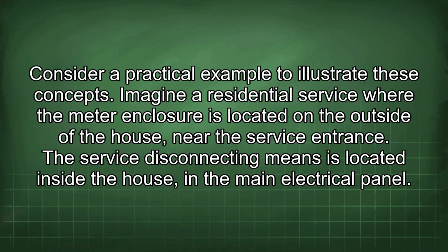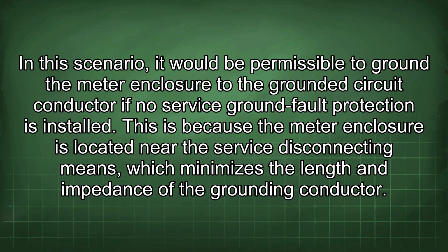Consider a practical example to illustrate these concepts. Imagine a residential service where the meter enclosure is located on the outside of the house, near the service entrance. The service disconnecting means is located inside the house, in the main electrical panel. In this scenario, it would be permissible to ground the meter enclosure to the grounded circuit conductor if no service ground fault protection is installed.